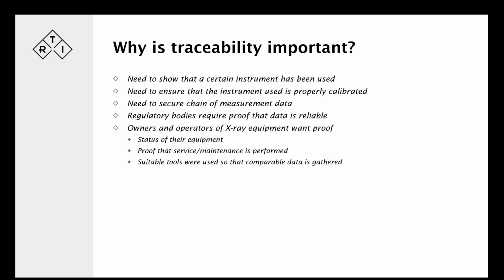They can also then ensure that comparable data is gathered. That could also be very important if they want to gather a larger database to be able to monitor the performance over time of different equipment. And also if they want to gather and compare data between different equipment, but at the same time. If you have the same generator in an X-ray machine, an owner may want to monitor that to see if the performance of those generators is the same, if they age the same when it comes to tubes. Do we see any changes in HVL over time?